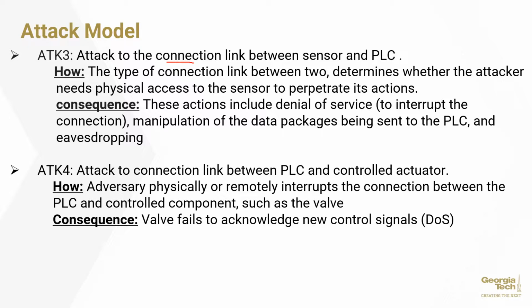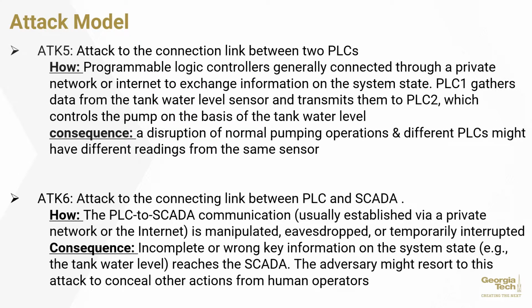Similarly, attack number 4 is on a connection link, but this time between the PLC and the controlled actuator. How this sort of attack happens is that the adversary physically or remotely interrupts the connection between the PLC and control components such as the valve, and it consequently might cause the valve to fail to acknowledge a new control signal.